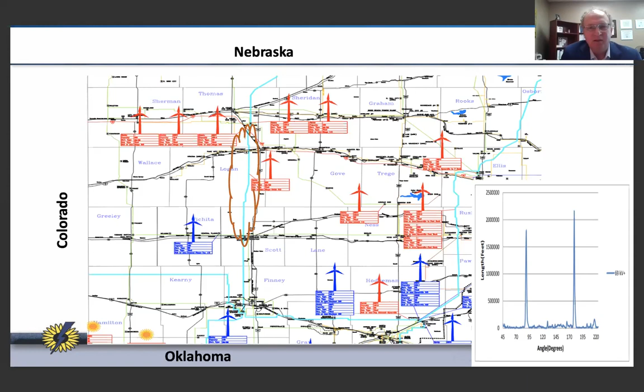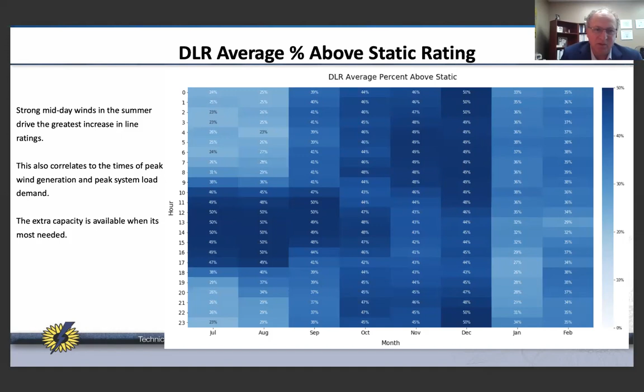So we'll go to the next slide. So the DLR average percent above static rating. And when we talk about static rating, this is the terminal limit static rating that we have on the line. It's about 800 MVA today. And when we applied the data, looking at the ambient temperature, the wind speed, and honestly, the angle where the wind hits the wire makes a big difference. The lowest increase we've seen on the rating is about 24% above the current ratings. And the highest I think we saw is 50%. And most of that happened in the midday hours of the month. The x-axis, you could see July 2020 through February 2021. And we didn't even have on average any hour that the dynamic line rating showed less rating than the terminal equipment limitation. Go to the next slide.